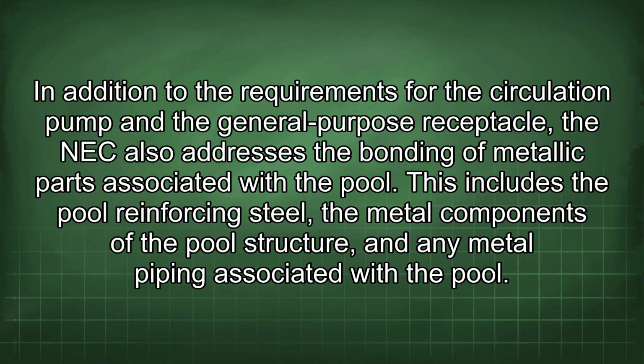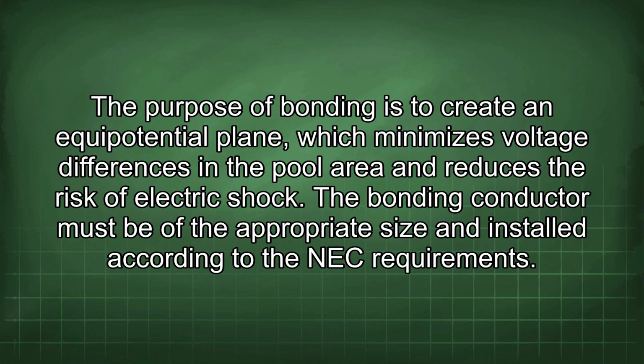In addition to the requirements for the circulation pump and the general-purpose receptacle, the NEC also addresses the bonding of metallic parts associated with the pool. This includes the pool reinforcing steel, the metal components of the pool structure, and any metal piping associated with the pool. The purpose of bonding is to create an equipotential plane, which minimizes voltage differences in the pool area and reduces the risk of electric shock.